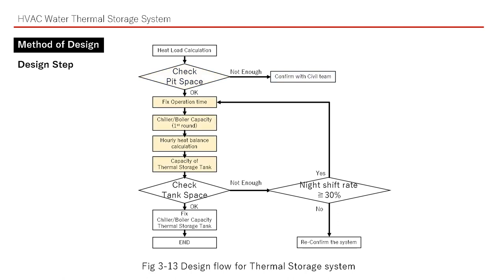Fix the operation time and temporarily select the chiller or boiler capacity. Perform an hourly heat balance calculation. Then temporarily select the capacity of the thermal storage tank based on that.